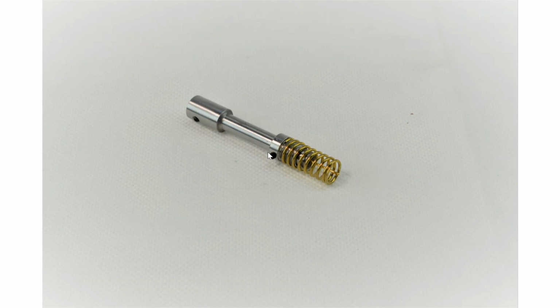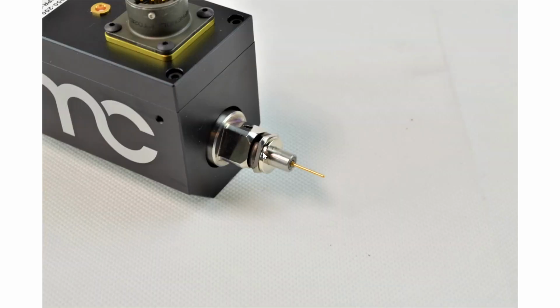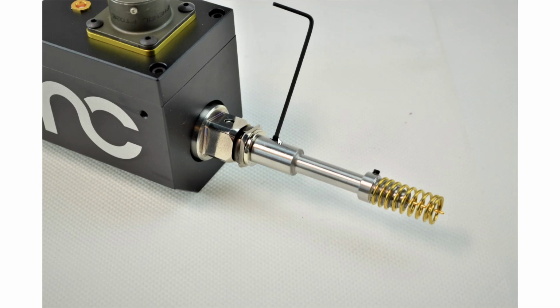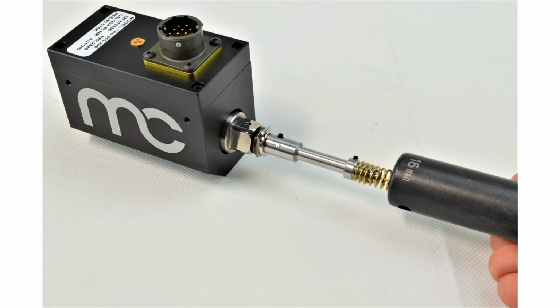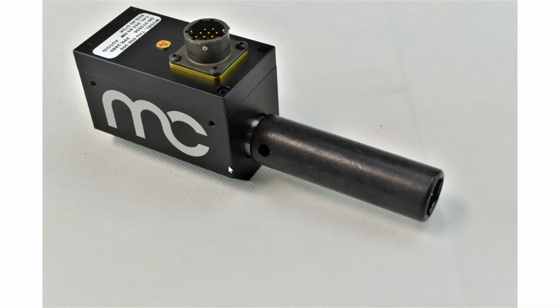So this is ready now. You can slide it inside this probe and then use the small wrench to tighten the set screw. Now it's all ready. Use the deep socket, slide it all in until it goes all the way into this square drive. Make sure the sockets go all the way in. If they're partially out, what will happen? It would exert pressure on this square and might break this. So make sure this socket is all the way in and touching this surface. Now it's ready to go.